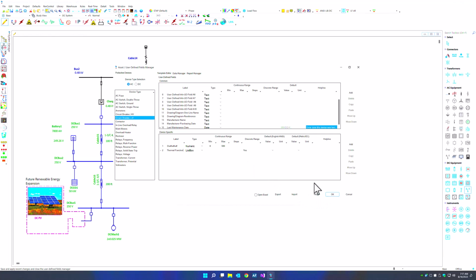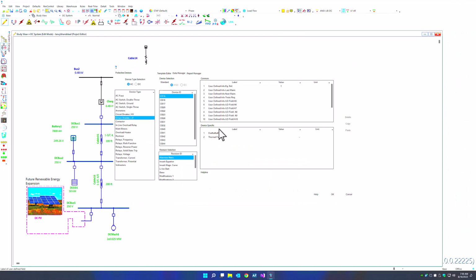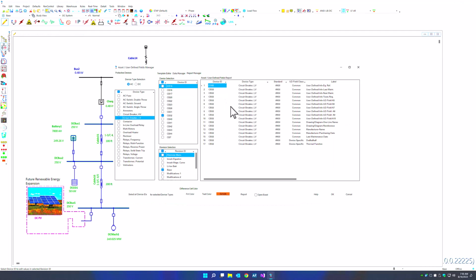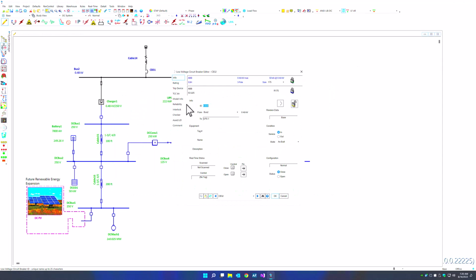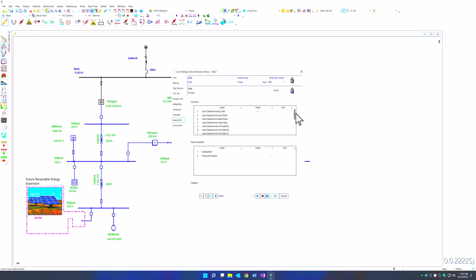but not necessarily used in any kind of simulation when it comes to protection or coordination. And then of course, within this template editor, you can also go inside the data manager, and within the data manager you can see all the changes that exist for those components in base or revision. You can also go inside the report manager and export the user-defined fields, including the 2 new fields that we just added that are device-specific. So we can open up our low voltage circuit breaker, go to the asset or user-defined fields, and we can see our last maintenance date, which is a date type field, as well as our device-specific fields.